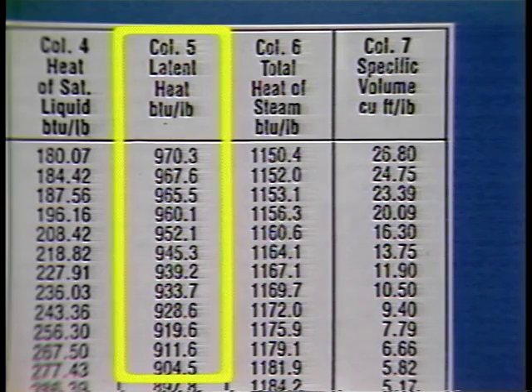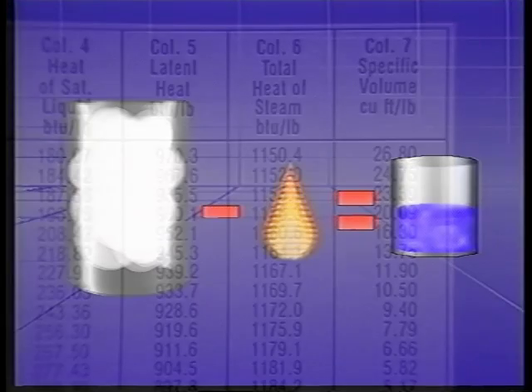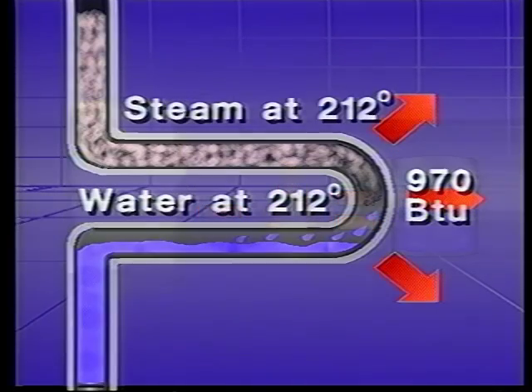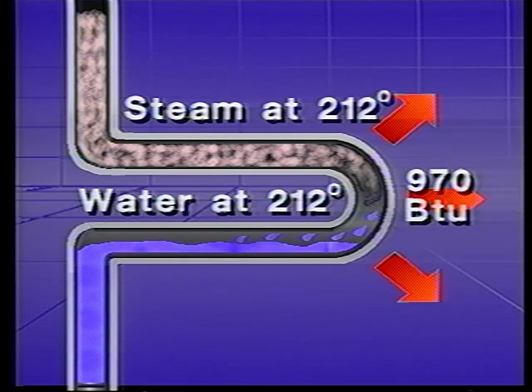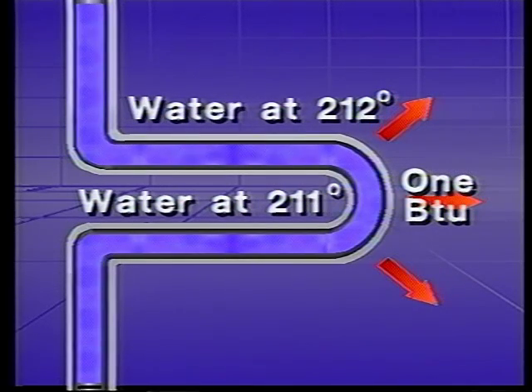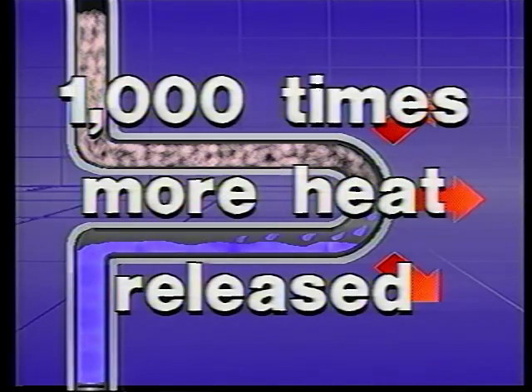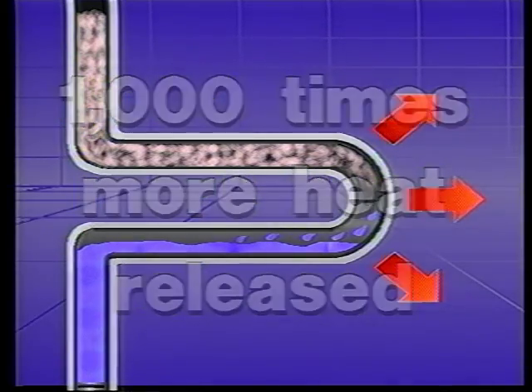The latent heat column best indicates why steam is such a good heating agent. All of the latent heat is released immediately when the steam condenses. At standard pressure, collapsing steam releases 970 BTUs per pound. In contrast, one pound of water at 212 degrees releases only one BTU as it cools to 211 degrees. The condensing steam gives up almost 1,000 times as much heat as the water without any change in temperature.